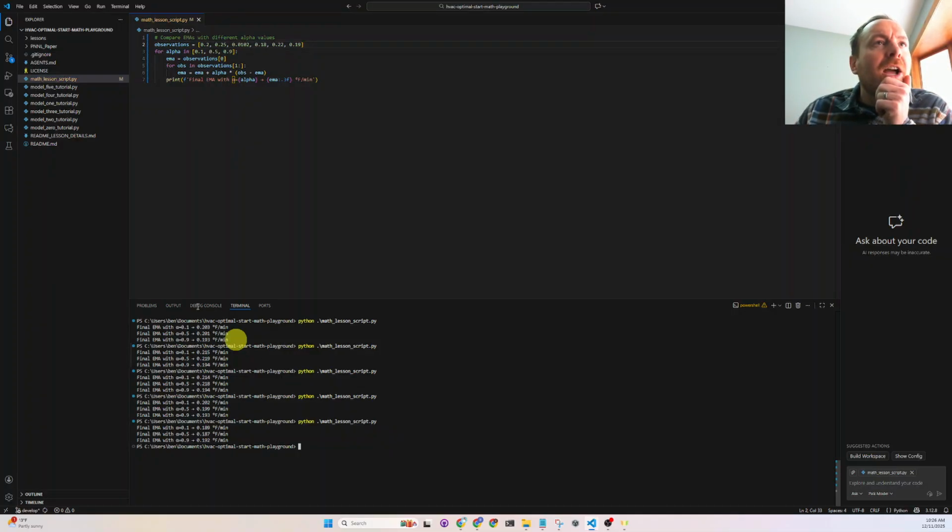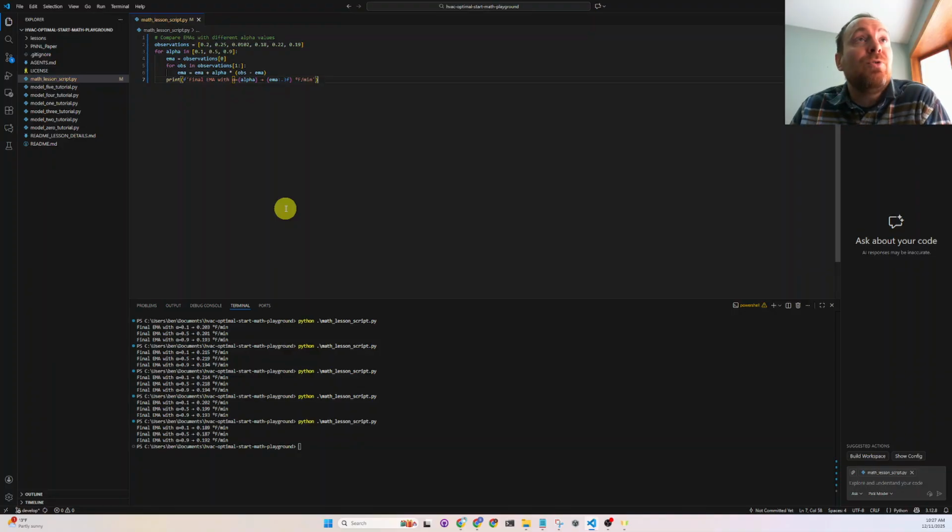So I think this would come in handy. Let's say you're running the linear model in a program, or whatever kind of optimal start algorithm coding language you're using, and you're getting some poor results, like you're overshooting or undershooting the actual minute calculations through the warm-up time. You could actually tune your alpha potentially to just be more accurate.